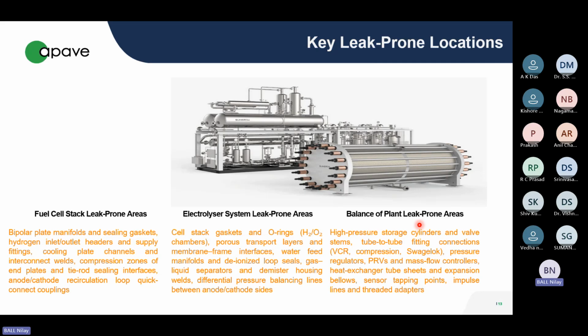In France, we do it. We have a complete space department. We have hydrogen and very highly sensitive helium leak test equipment in India, and we do it for very critical heat exchangers. We insert helium leak test detection tubes into the heat exchanger tubes, because in tubes, if you have a leakage, the whole plant performance comes down. So we use helium leak testing there. We have a couple of very sensitive equipment in India, used in most of our clients' areas. It's an expensive test.